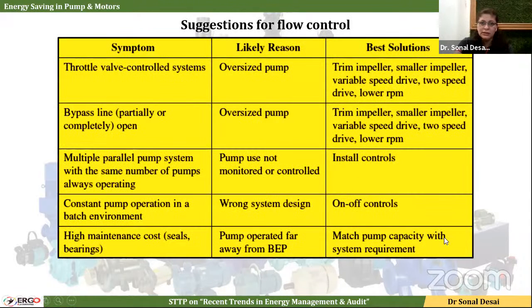These are the normal observations, the likely reasons, and what we should do to achieve energy efficiency. If a throttle valve is used, it is most of the time an oversized pump. So if possible, trim the impeller, use the smaller impeller. It's not always required to trim the impeller. You can have two sets of impellers. Whenever you buy a pump from a manufacturer, the same supplier, the same OEM can also supply you another impeller of a lesser diameter. So you can keep the original impeller aside and go with the smaller impeller, and you can use it to reduce the pump operating cost.